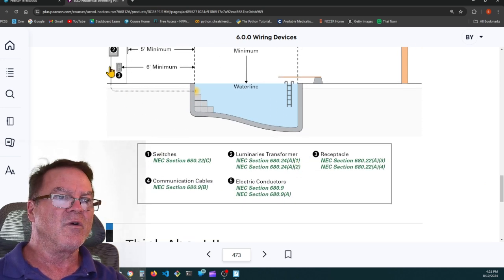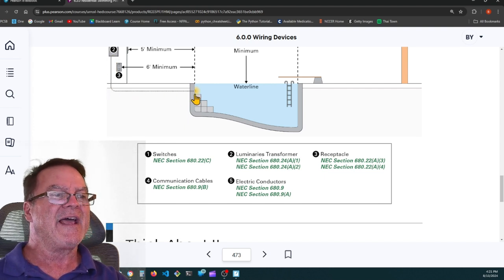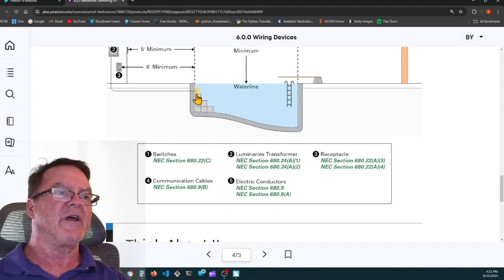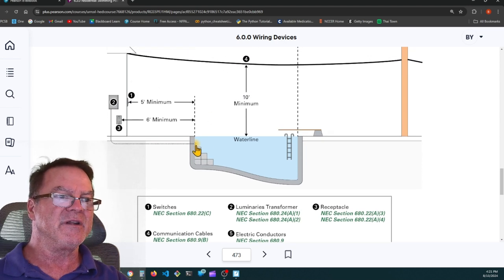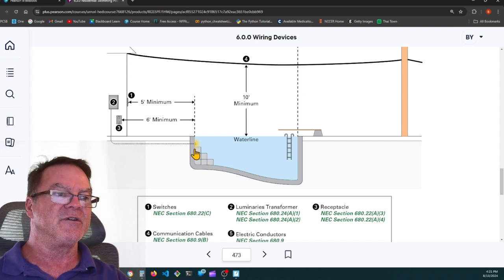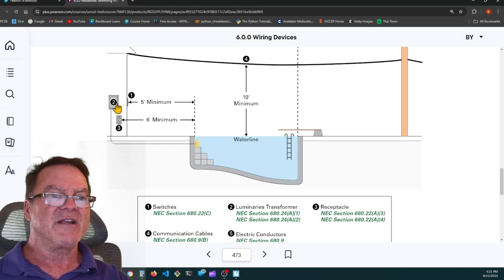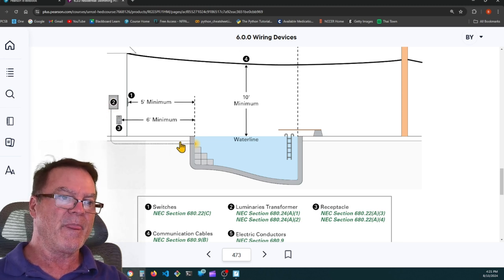The luminaire transformer. You don't have to have low voltage lighting in a swimming pool. I think it's a great idea. I would recommend it, but you can have 120 volt lighting in your swimming pool. The caveat is that you have to have an isolation transformer that is 120 to 120. It's a 1-to-1 isolation transformer, and it has to be fed off of a GFCI circuit, so that if anything ever goes wrong, it's going to trip the circuit and disconnect the power before anyone gets hurt.